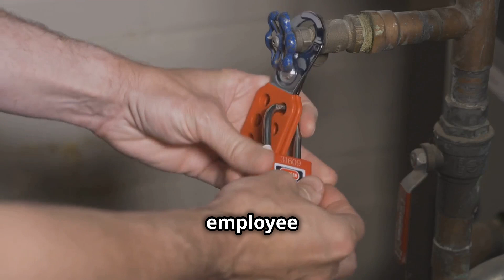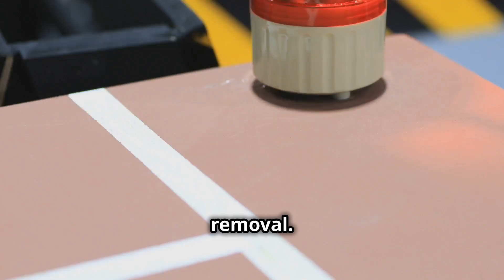The tag should be durable, weather-resistant, and securely attached to the energy isolating device in a manner that prevents accidental removal. It should be clearly visible and legible, even in low light conditions. The use of standardized tag colors, symbols, and wording enhances clarity and reduces the risk of misinterpretation.